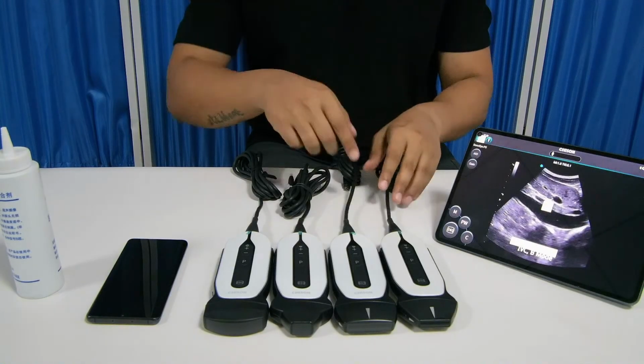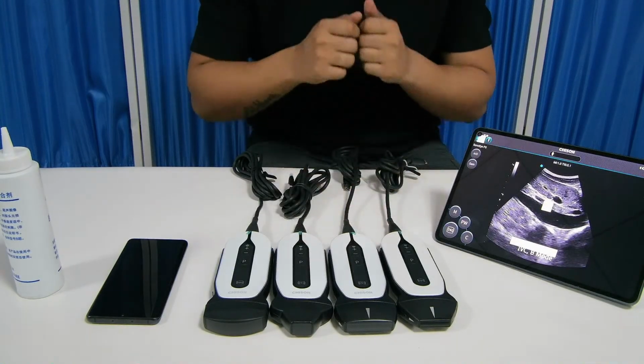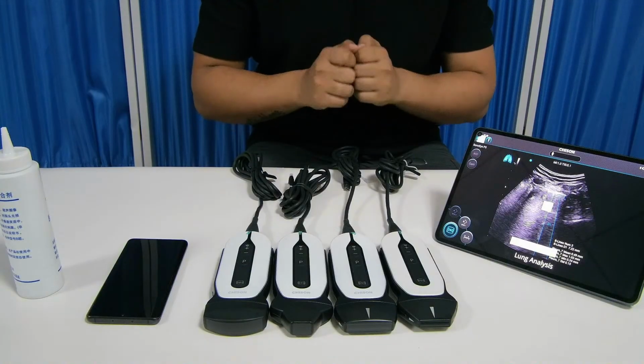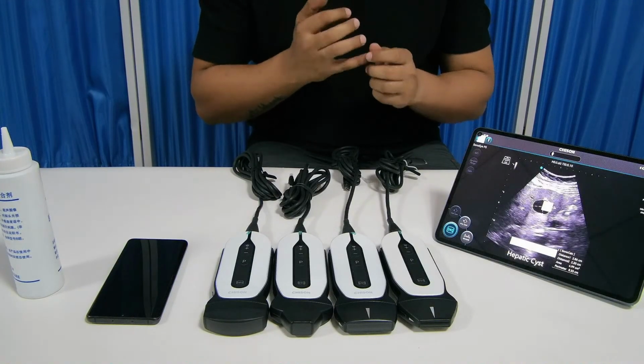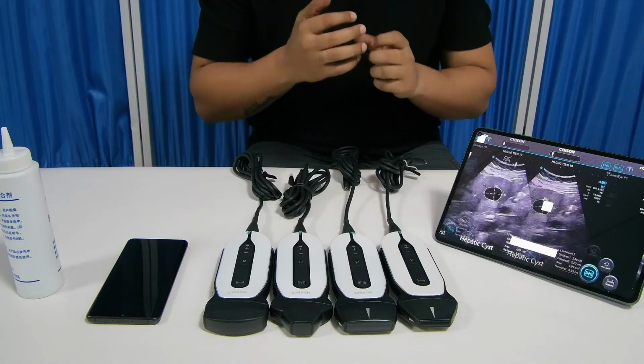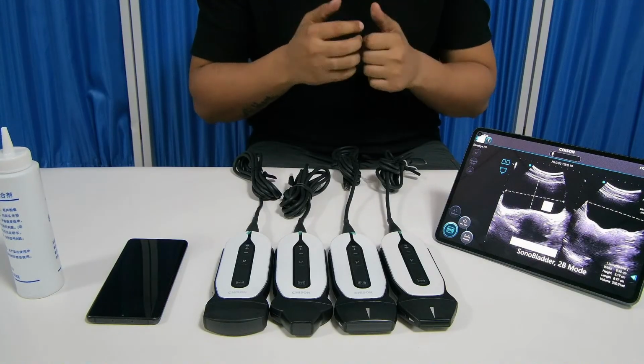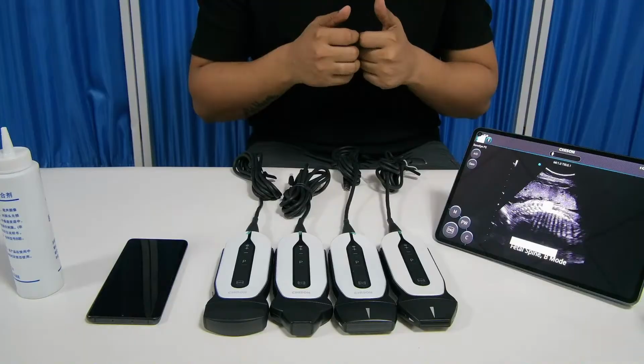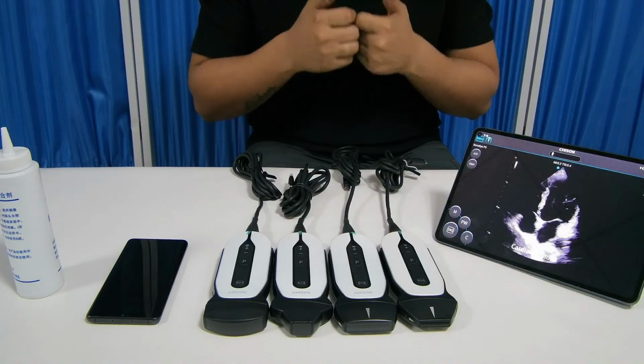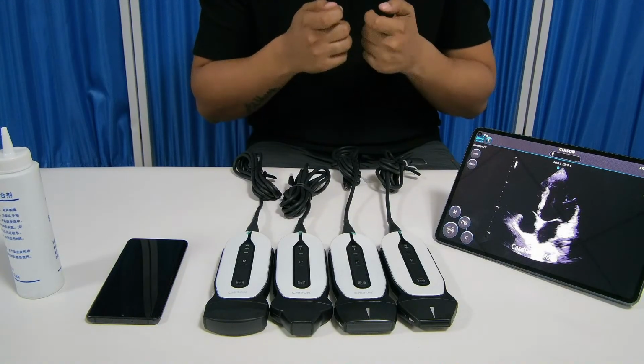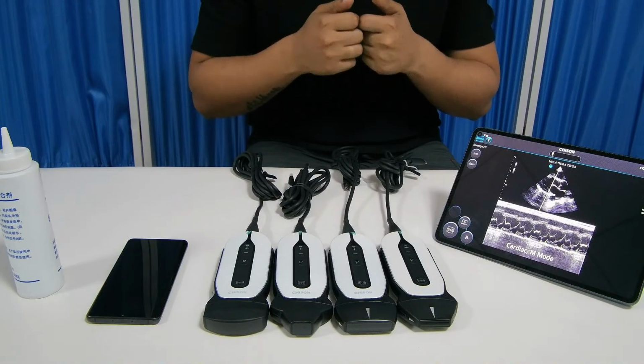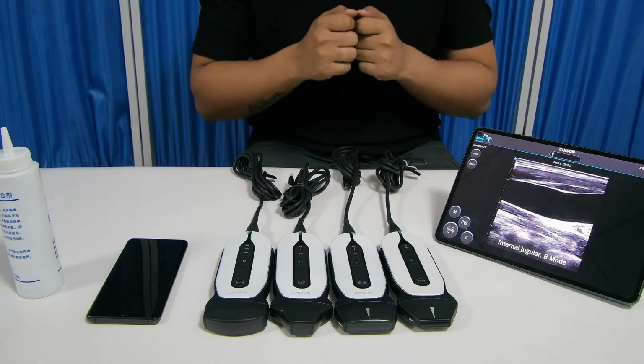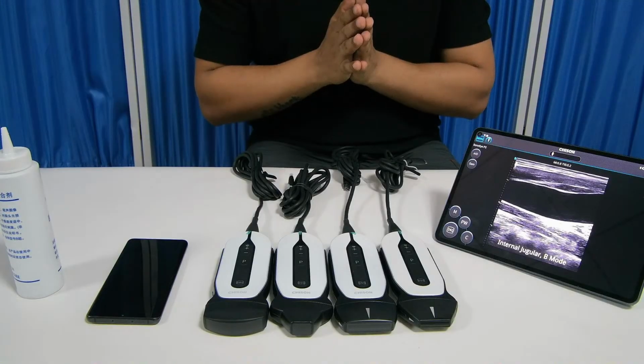Another big advantage of SonoEye transducer is that all the transducers are tested against any kind of vibration, shock, any kind of unintentional drop or fall. The SonoEye series is tested with all the standards of US military standard of 810G. And the transducers are also IP67 rated to protect against any kind of liquid ingress. Let's take a look at how these transducers work.